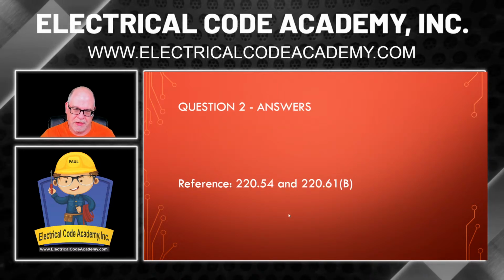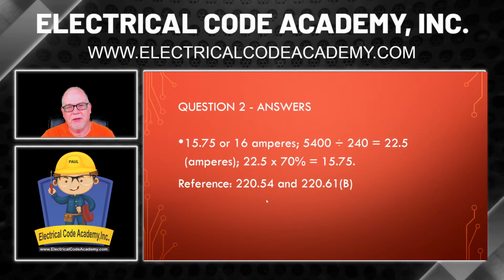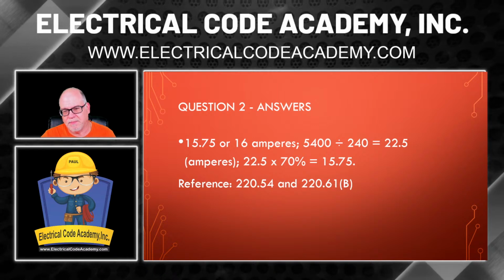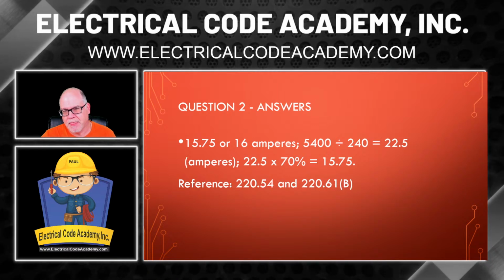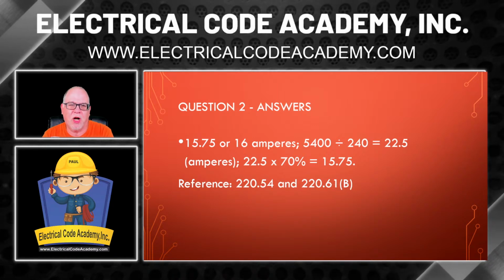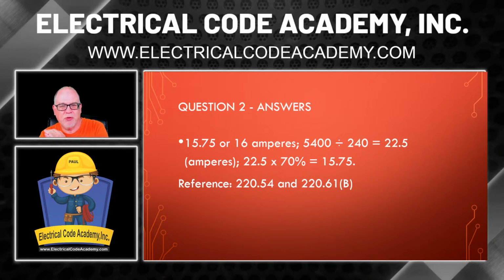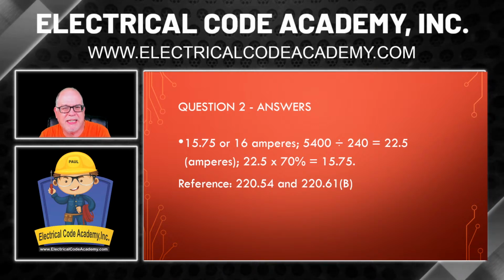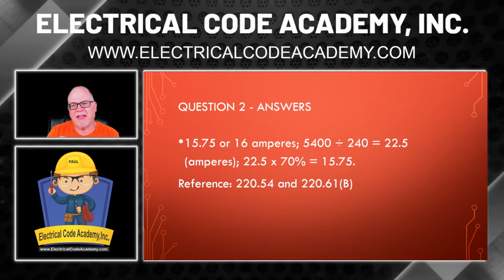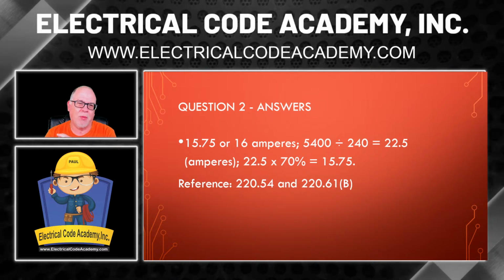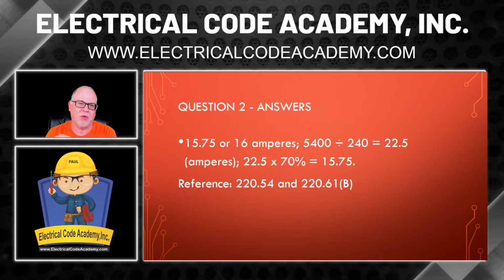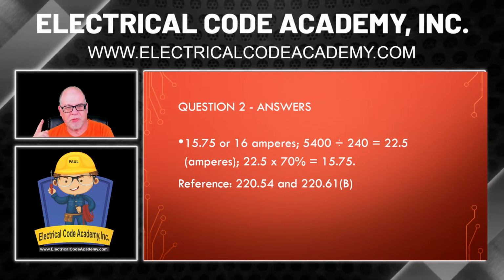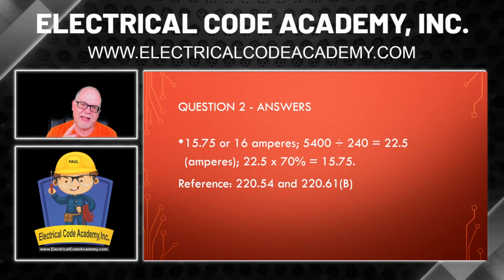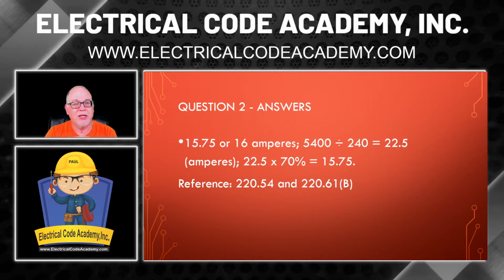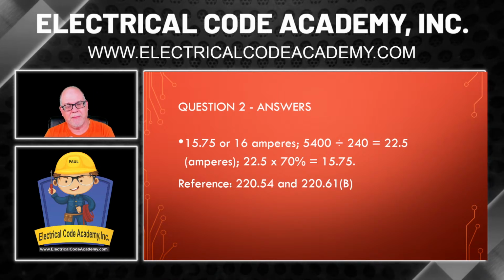And we know there's a code reference. And there you go. As you can see here, it's simply 5,400 divided by 240 is 22.5. We did that earlier. But we multiply that by 70%, or as I always like to do, I would like to convert this to a decimal. So I take that 70%, go from the right, move it two spaces to the left. So it's 0.70. You learn all that kind of stuff in our program.